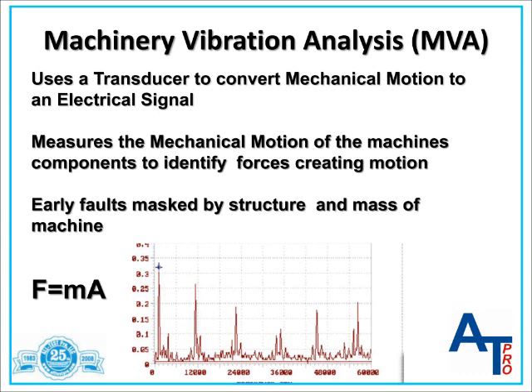During that time, tremendous strides have been made in implementing these programs and understanding, identifying, and determining the severity of the mechanical faults this technology can identify. Machinery vibration analysis relies on the mechanical forces created inside the rotating machine to cause the casing of the machine to respond to the applied force. According to Newton's second law of motion, force equals mass times acceleration. The mechanical motion created by the internal forces is measured by a transducer, which converts this mechanical motion to an electrical signal.